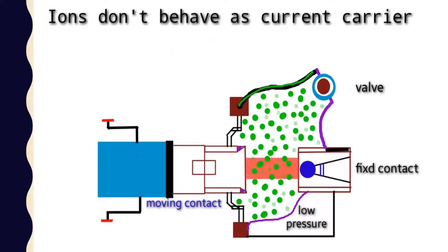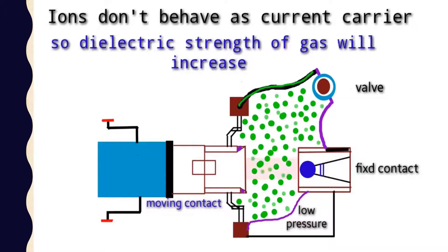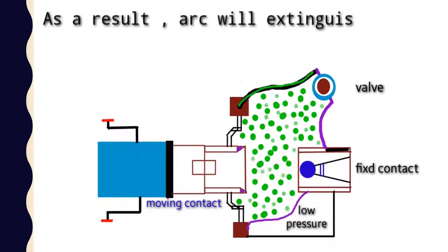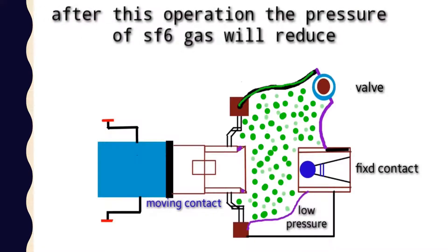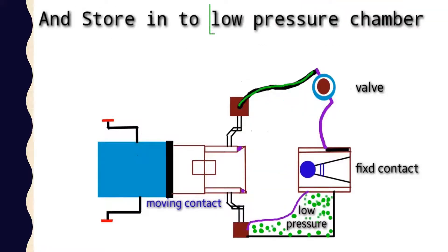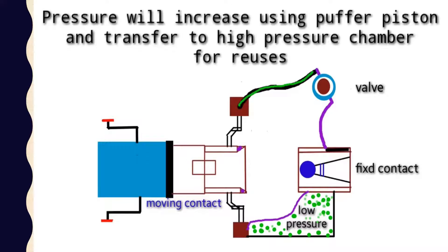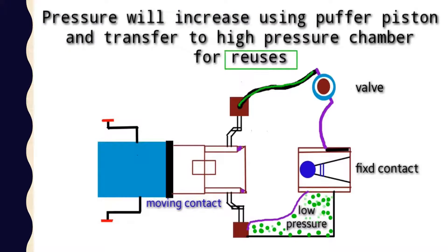The SF6 gas converts the free electrons into ions. These ions do not behave as current carriers, which causes the dielectric strength of the gas to increase. This causes the arc to be completely extinguished. After this operation, the SF6 gas pressure reduces and it is stored in the low pressure chamber. Using the puffer piston pressure, the gas pressure is increased again and it is reused.